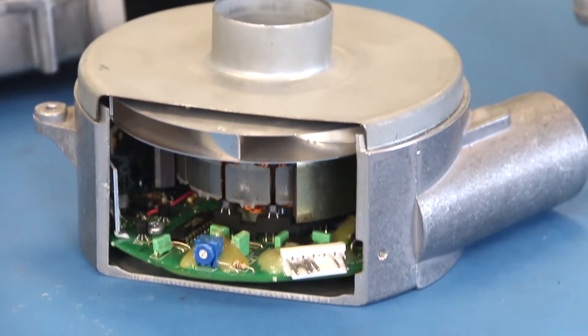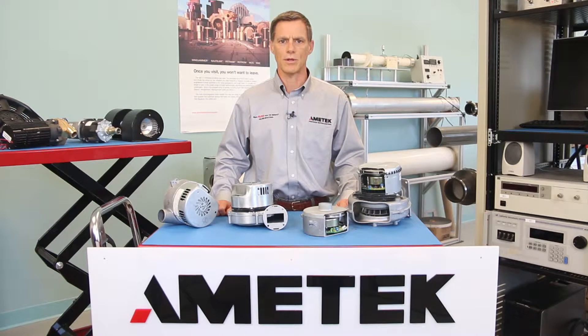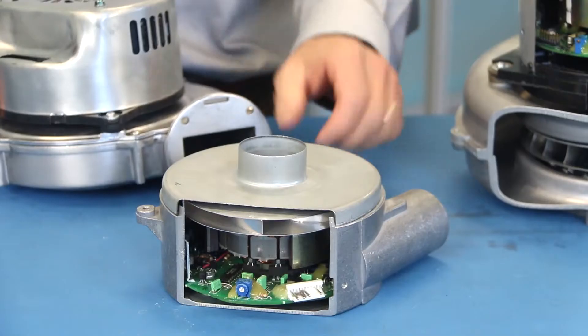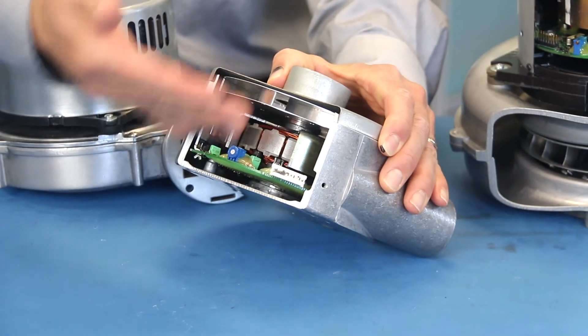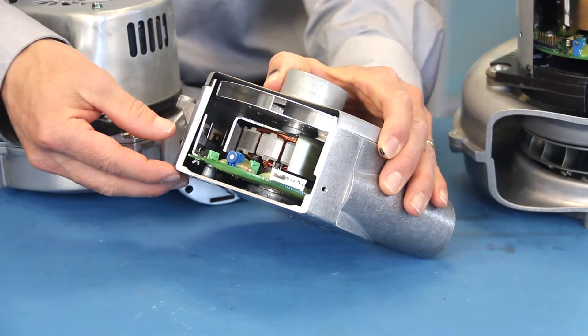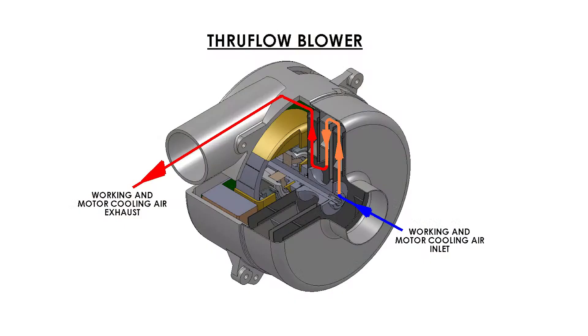A through-flow blower design does not have a steel motor enclosure, and the power connection is made through the die-cast aluminum blower housing. In a through-flow design, the working air and motor electronics cooling air are one and the same, being intermixed within the blower. This provides for a smaller overall blower package.